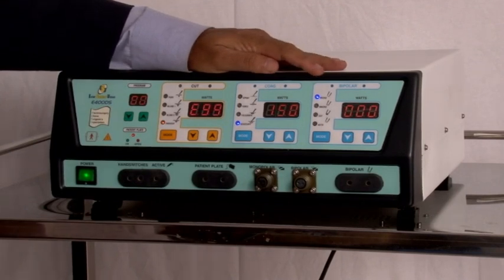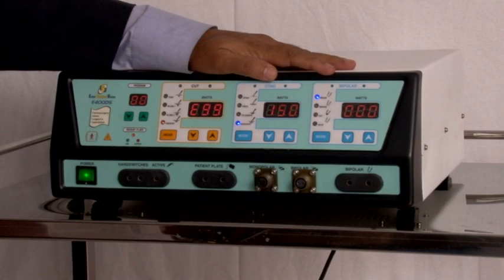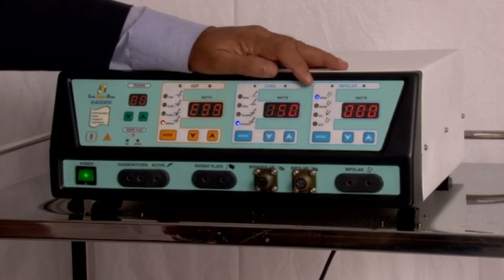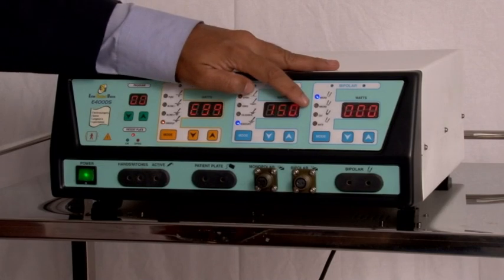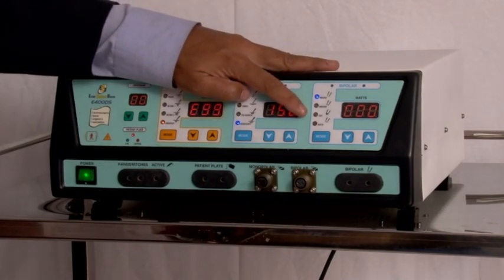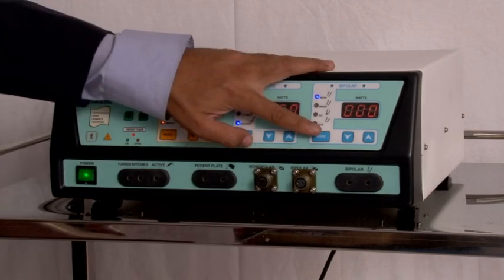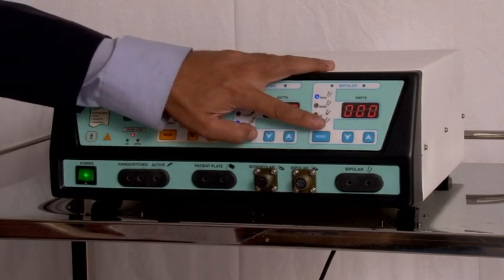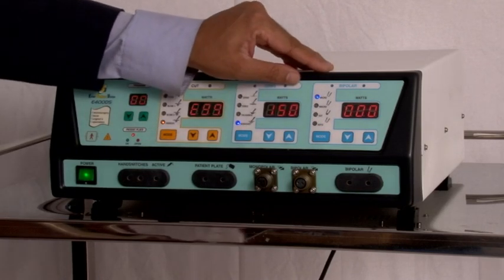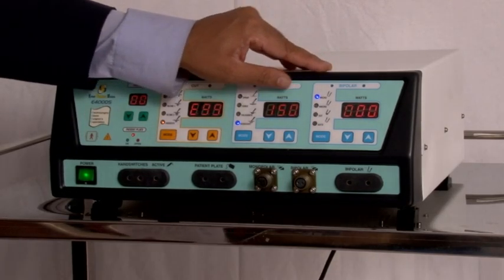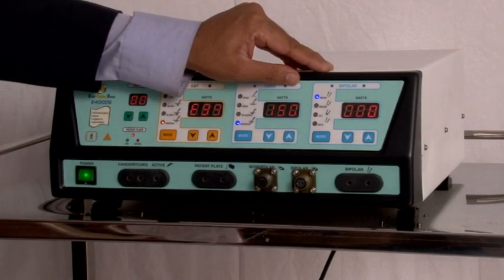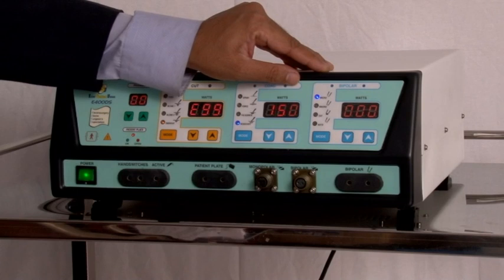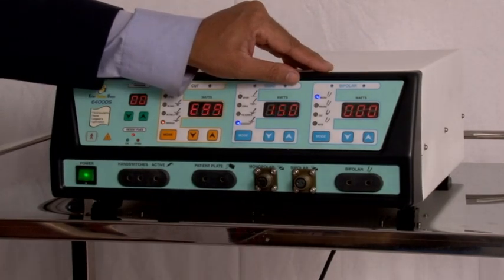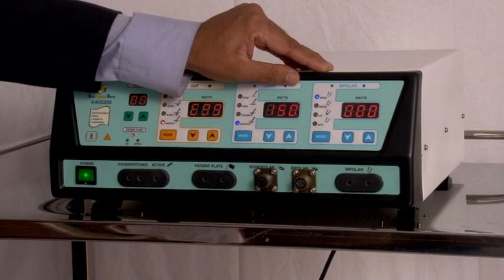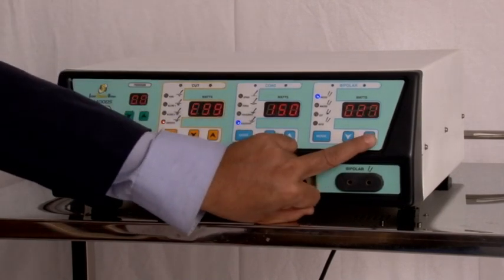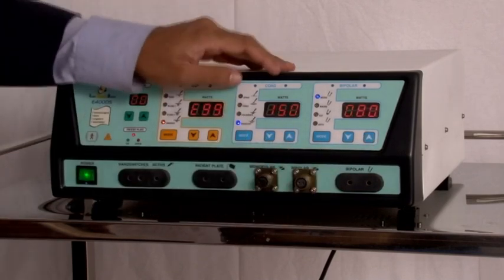The other type of output is bipolar output. In bipolar output, we have four modes: microbipolar, macrobipolar, bipolar cut, and autobipolar. First mode in bipolar is microbipolar, a pure sinusoidal waveform with low voltages, which assures precise coagulation without damaging the adjacent tissues. Microbipolar is preferred by ENT, neuro, and ophthalmic surgeons. Microbipolar has a maximum output of 80 watts.